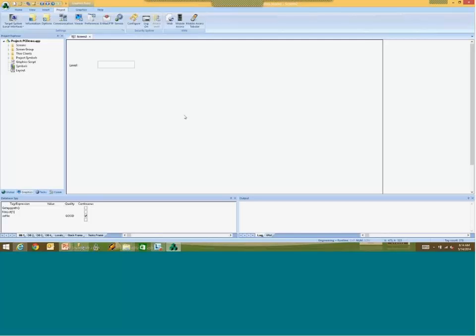If you select send every state, even if you click the button faster than the cycle of the driver, the command 1 and 0 both will be buffered in a communication queue, and when the driver eventually executes the commands, it sends the value 1, and then it will send the value 0. So depending on the application, if you have jogging, those kind of commands, it is a good practice to select send every state. Otherwise, you can select send last state to avoid buffering information and sending all the information to the PLC if you just care about the last value.